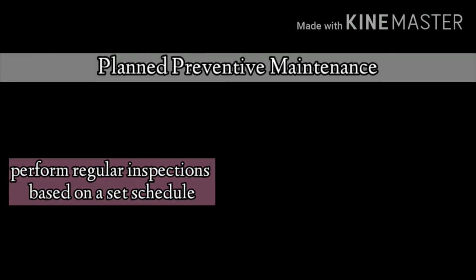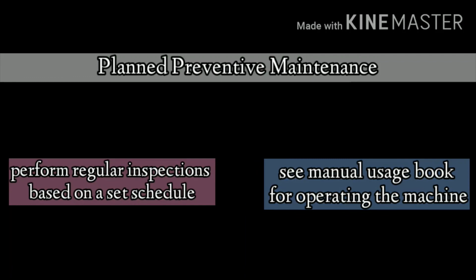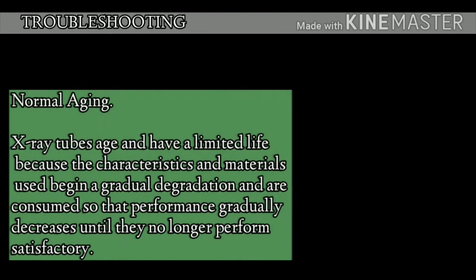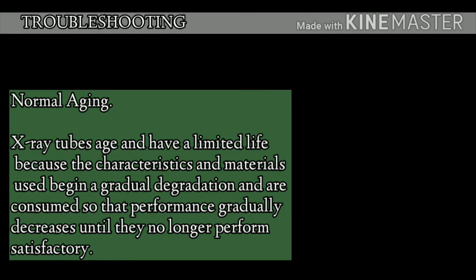Planned preventive maintenance. First, perform regular inspection based on a set schedule. Second, see manual usage book for operating the machine. Troubleshooting for X-ray machine. First, normal aging. X-ray tubes age and have a limited life because the characteristic and material used begin a gradual degradation and are consumed, so that performance gradually decreases until they no longer perform satisfactorily.